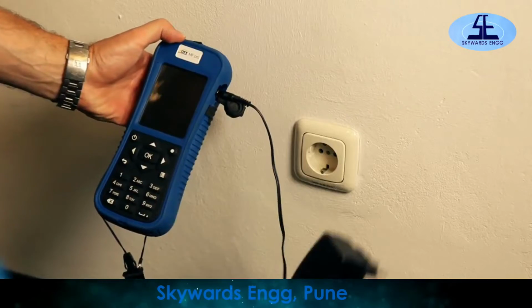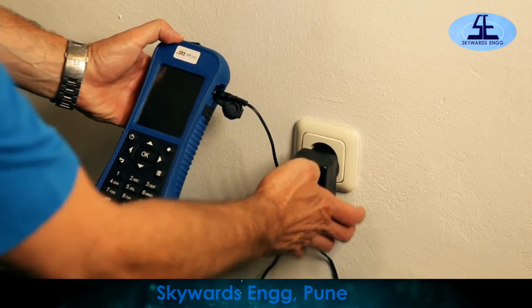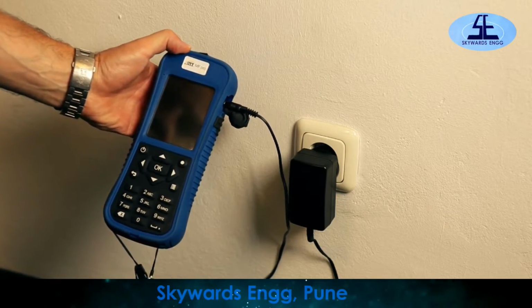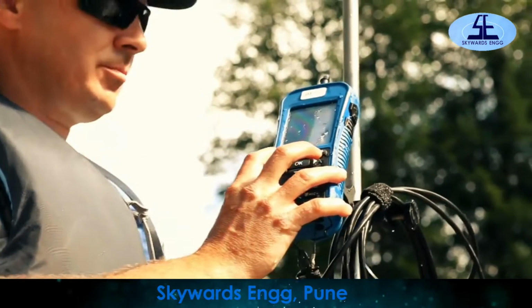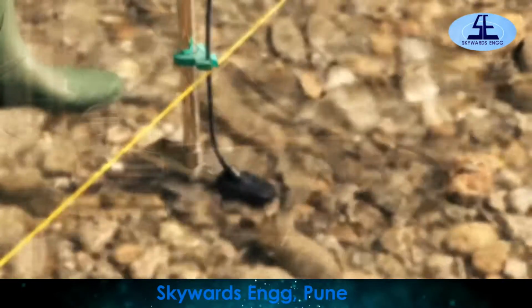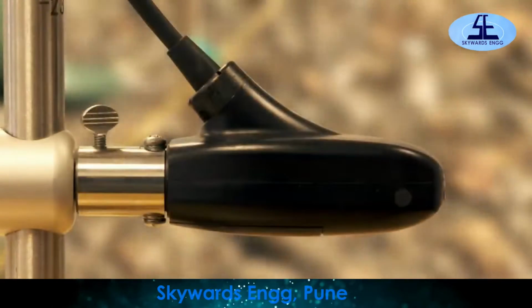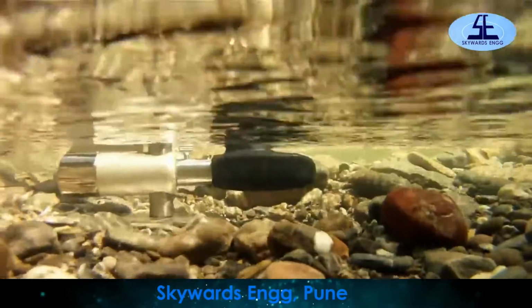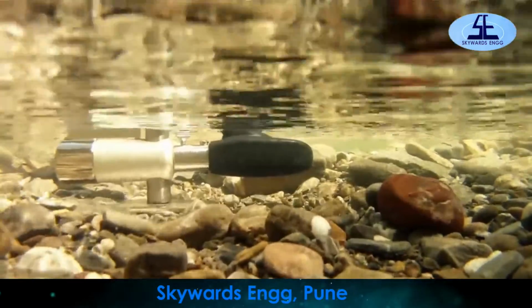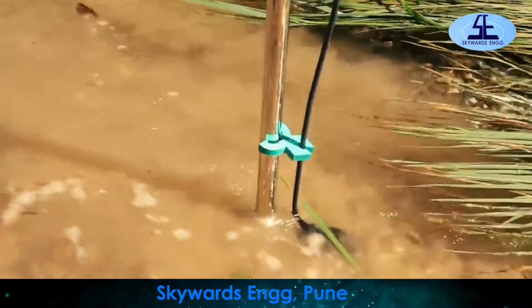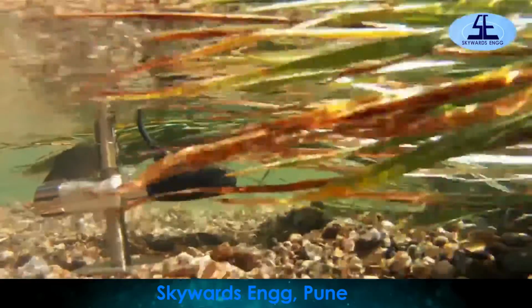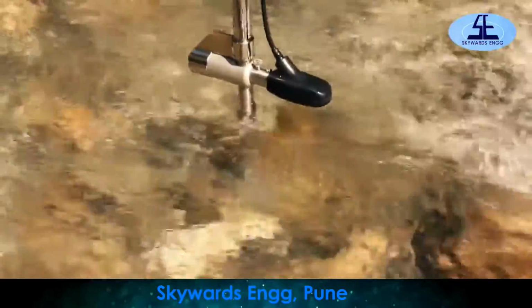The built-in rechargeable battery lasts for 18 hours when the unit is intensively in use. The measuring principle, in combination with the compact sensor shape with good flow characteristics, allows reliable measurement even at the lowest flow velocities and even in very shallow water. It can be used without any compromises even in water that contains sediment or weeds, and also in turbulent flow conditions.